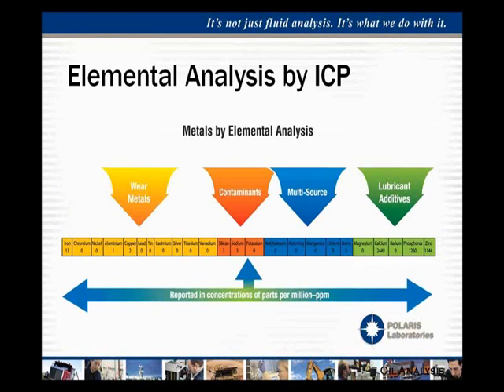Now we're going to talk specifically about what these different tests are. For elemental analysis, we use an inductively coupled plasma spectrometer, which gives us a range of 24 different metal elements. As you can see in this chart, iron, chrome, nickel, aluminum, all the way over to vanadium are typically considered wear metals. Then we have three elements — silicon, sodium, and potassium — that are typically contaminants.